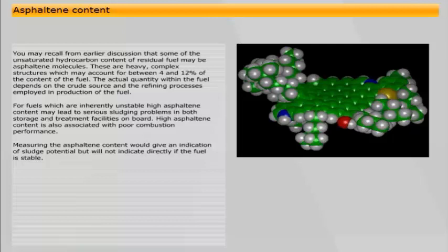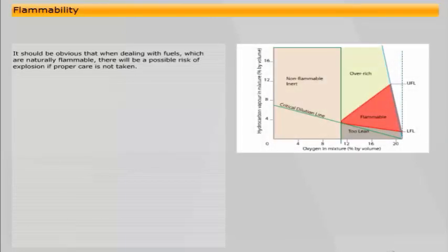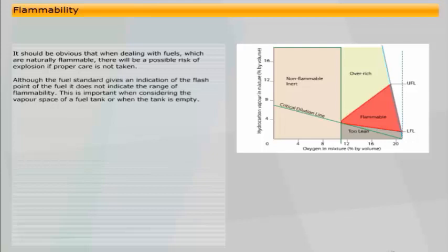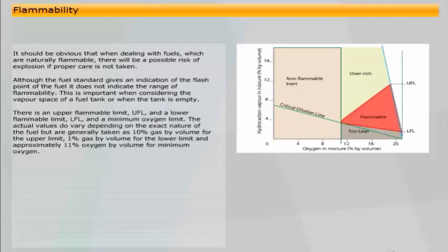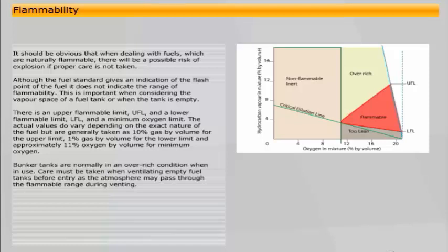It should be obvious that when dealing with fuels which are naturally flammable, there will be a possible risk of explosion if proper care is not taken. Although the fuel standard gives an indication of the flash point of the fuel, it does not indicate the range of flammability. This is important when considering the vapour space of a fuel tank or when the tank is empty. There is an upper flammable limit, UFL, and a lower flammable limit, LFL, and a minimum oxygen limit. The actual values do vary depending on the exact nature of the fuel, but are generally taken as 10% gas by volume for the upper limit, 1% gas by volume for the lower limit, and approximately 11% oxygen by volume for minimum oxygen. Bunker tanks are normally in an over-rich condition when in use. Care must be taken when ventilating empty fuel tanks before entry as the atmosphere may pass through the flammable range during venting.